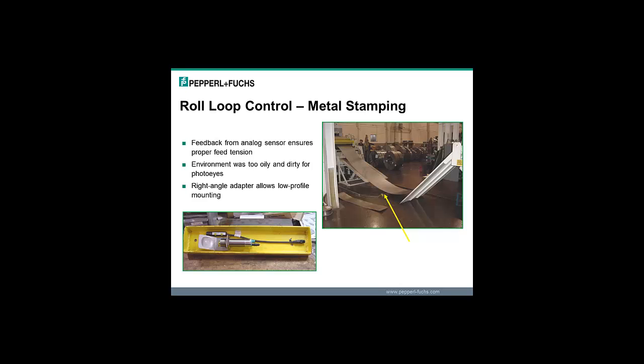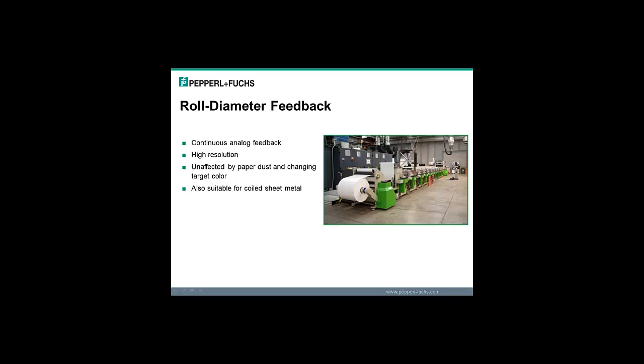The environment was originally going to be for a photo eye. You can see down there a sensor mounted in that right angle bracket. That's an ultrasonic. And then to the right of it is a photo eye. But the oils and the dirt that came off of the sheet metal caused problems for the photo eye. You were constantly cleaning the lens. So the right angle transducer allowed that ultrasonic to fit in that little trough there and basically take up about the same mounting height as the photo eye did. So that was roll loop control in a metal stamping application.